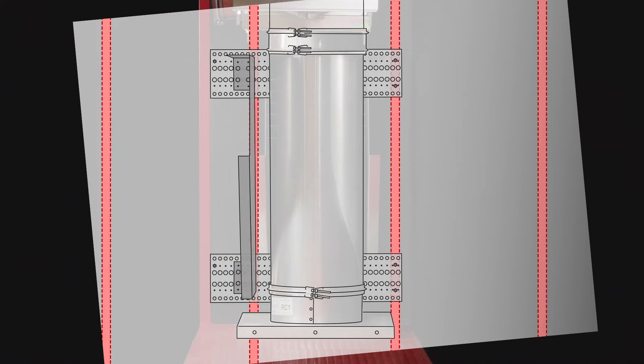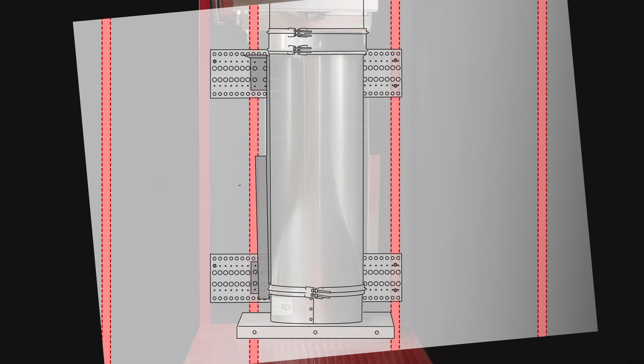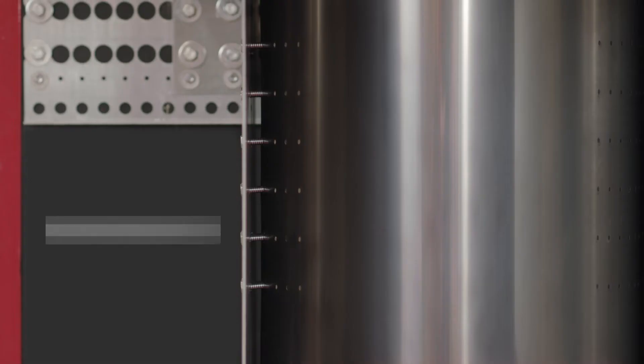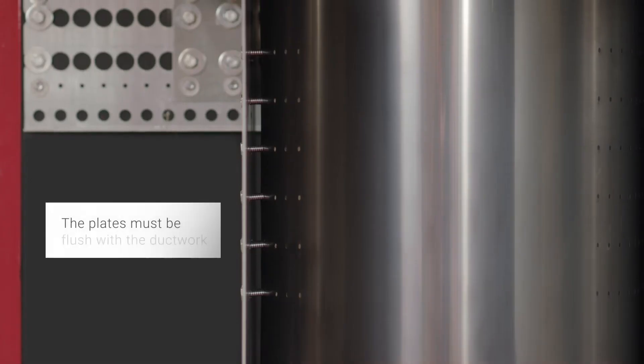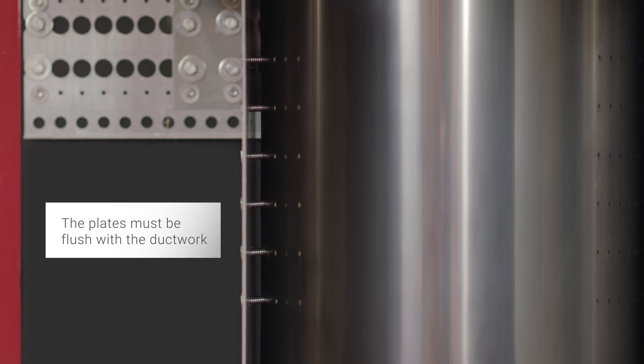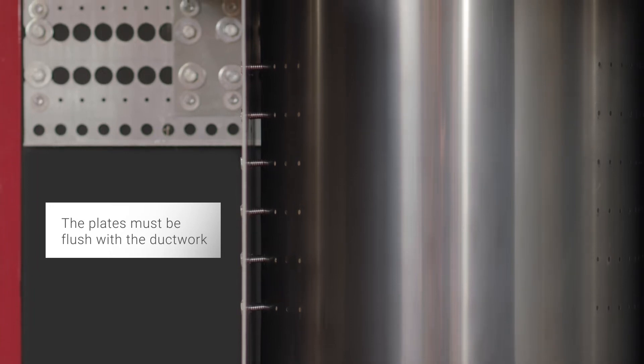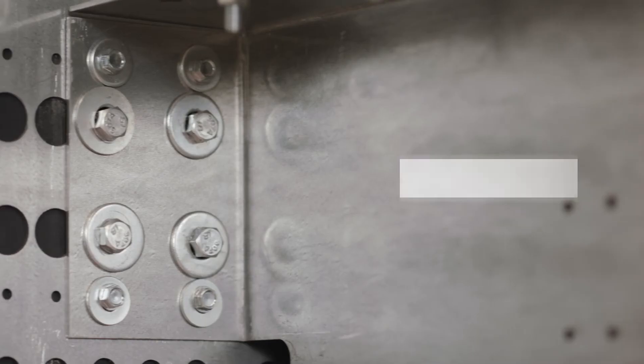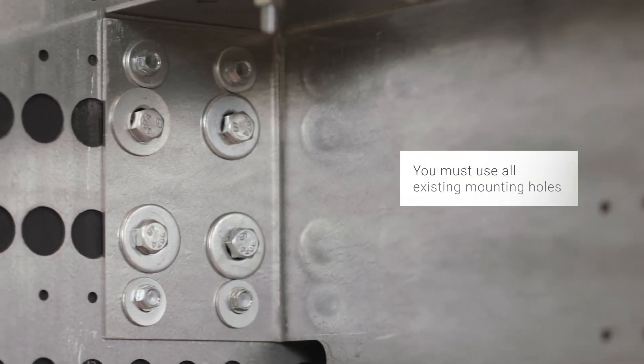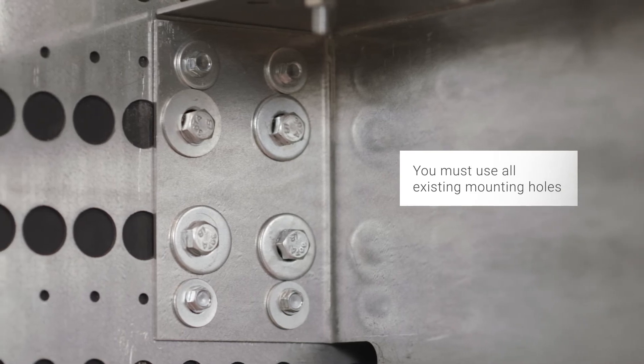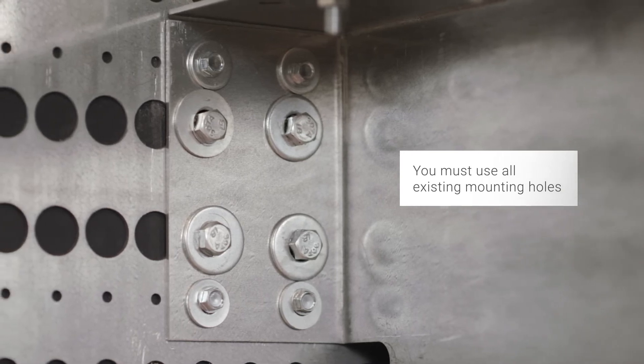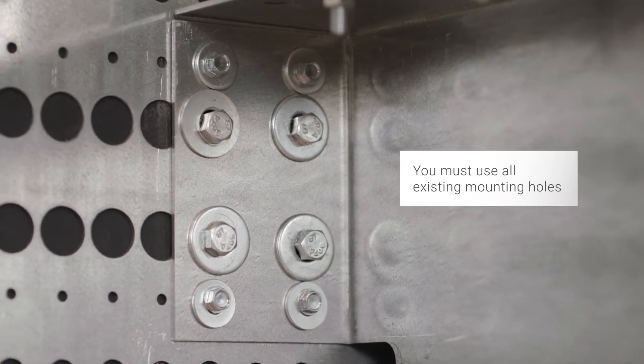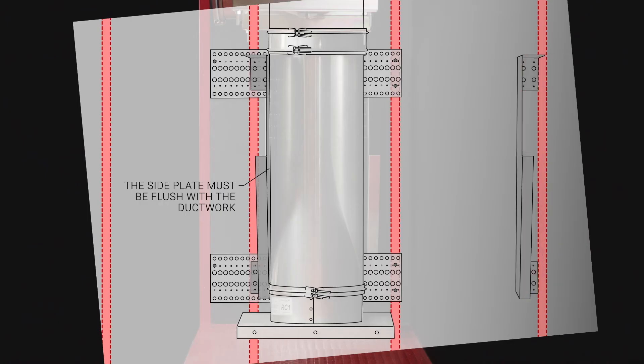Next, install the side plate that will secure directly into the aligned stud. You must install the plate flush with the ductwork. You must also attach the plate using all existing mounting holes to both the upper and lower supports.